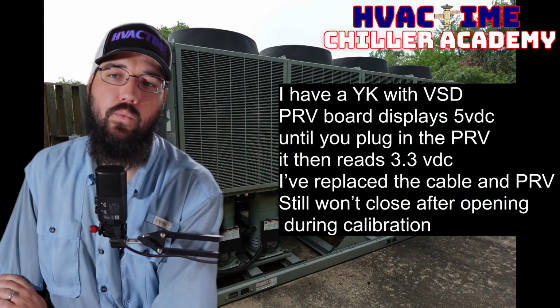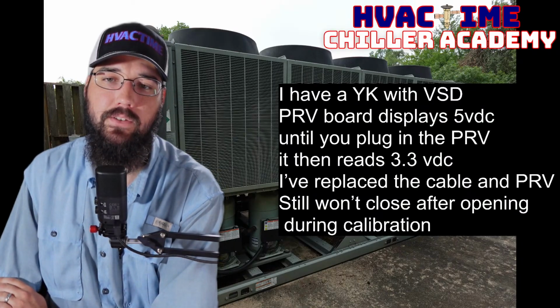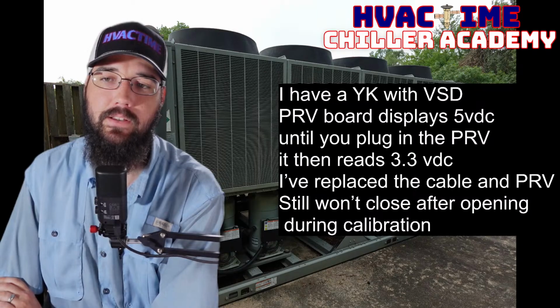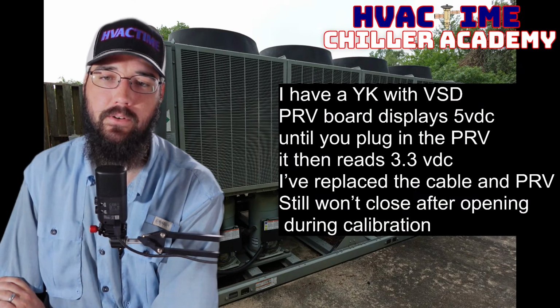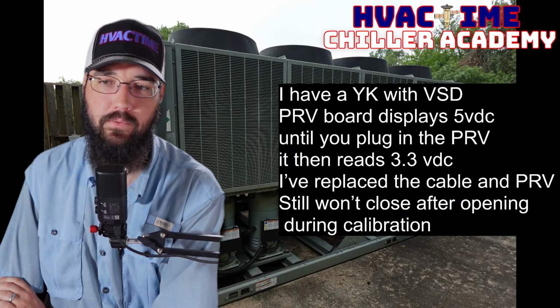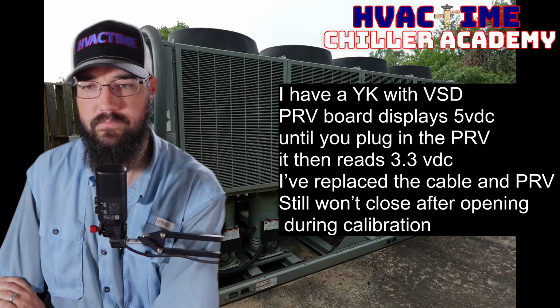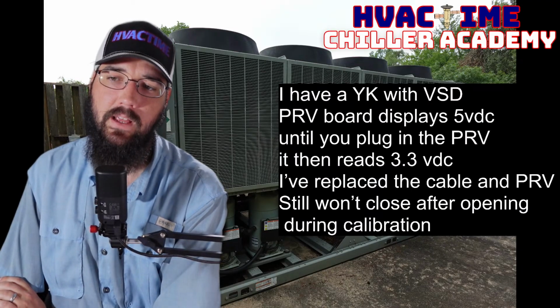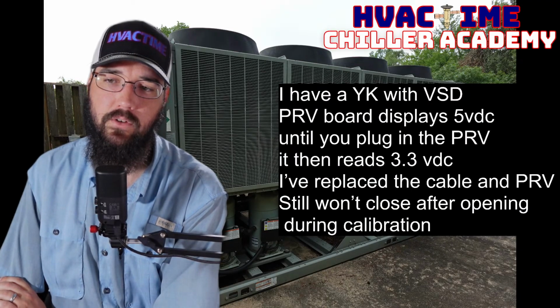I have a YK with a VSD PRV board, displays 5 VDC until you plug in the PRV. It reads 3.3 VDC. I replaced the cable and the PRV still won't close after opening during calibration.